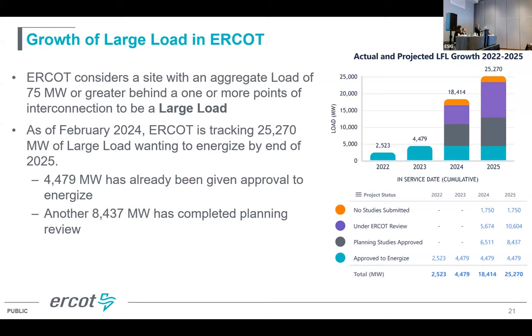In this slide, I'm only talking about large loads, what we call large loads within ERCOT. This has been an issue starting very recently, in the last 3-4 years. Prior to that, we were able to incorporate large loads through our normal interconnection and planning process. But what changed is the influx of large data centers and crypto loads that wanted to connect within ERCOT. So we have been working with our stakeholders to define these loads, because the pace at which they interconnect, and the timelines, are really short.